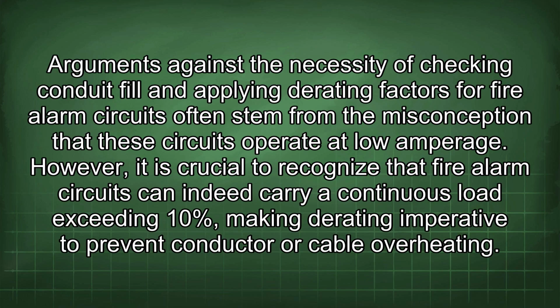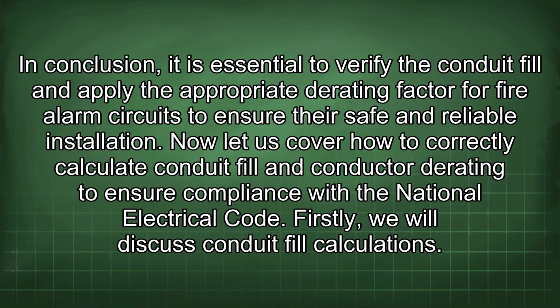Arguments against the necessity of checking conduit fill and applying derating factors for fire alarm circuits often stem from the misconception that these circuits operate at low amperage. However, it is crucial to recognize that fire alarm circuits can indeed carry a continuous load exceeding 10%, making derating imperative to prevent conductor or cable overheating. In conclusion, it is essential to verify the conduit fill and apply the appropriate derating factor for fire alarm circuits to ensure their safe and reliable installation.